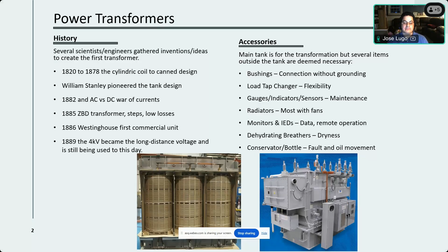So most of the time, for anything that's above 5 MVA and below 50 MVA, you might have a gas inert bottle, which is basically gas on top of the main tank inside that maintains a pressure in there, which you will have a gauge to indicate. That pressure will maintain the oil level on the transformer if there is a fault, and it gives you all kinds of indications. So there's quite a bit of things that you could do with a transformer. And again, this is all to maintain the transformer, make sure that it lasts for about 4 decades, which is the ultimate goal.